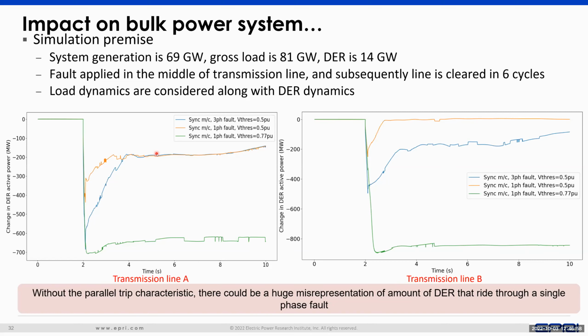Now, if you apply that same fault as a single line to ground fault, but don't consider transformer winding configurations and their impact on tripping, your simulation might still tell you that only around 200 megawatts of DER would trip. But if you actually consider the impact of different winding configurations, there's close to 700 megawatts of DER that could trip.